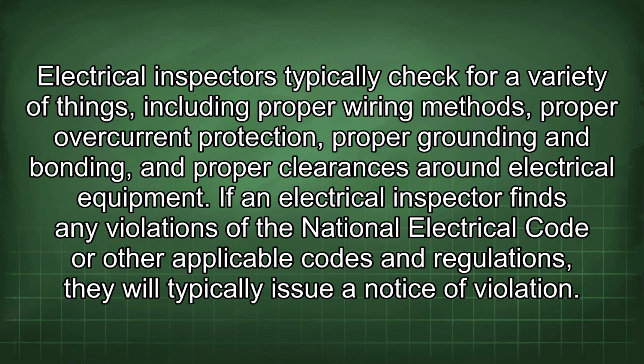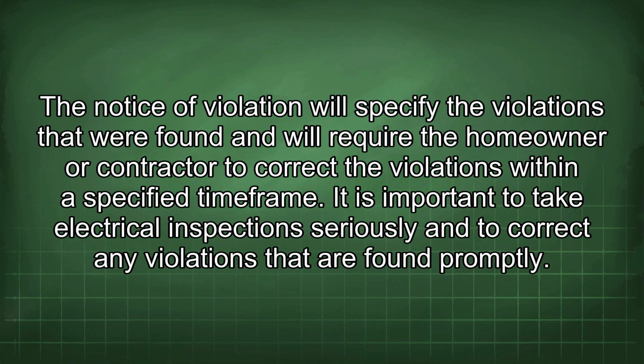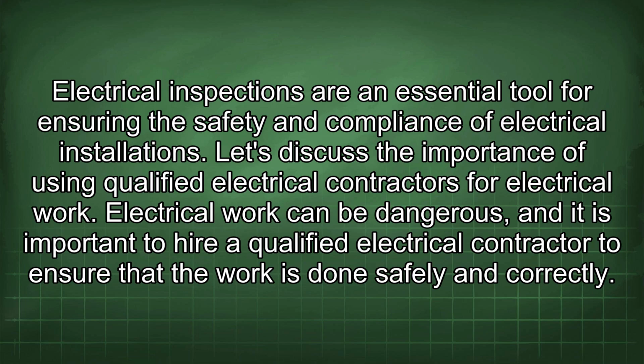If an electrical inspector finds any violations of the National Electrical Code or other applicable codes and regulations, they will typically issue a notice of violation. The notice of violation will specify the violations that were found and will require the homeowner or contractor to correct the violations within a specified time frame. It is important to take electrical inspections seriously and to correct any violations that are found promptly. Electrical inspections are an essential tool for ensuring the safety and compliance of electrical installations.